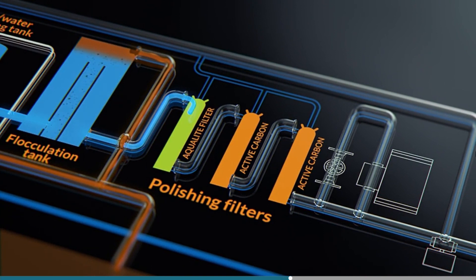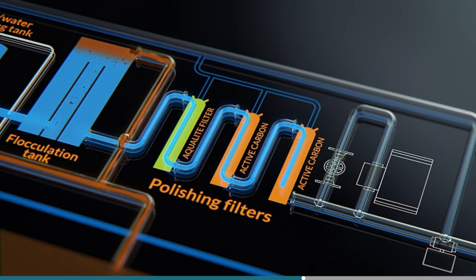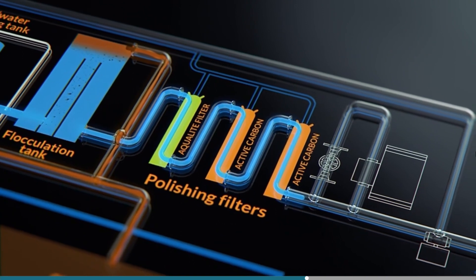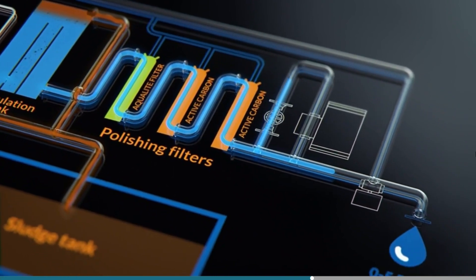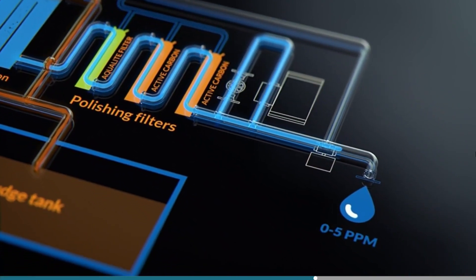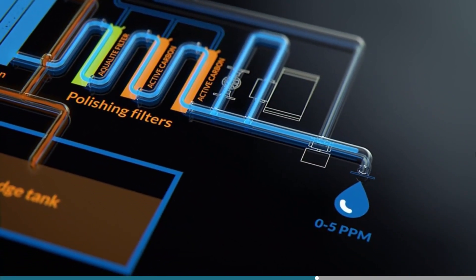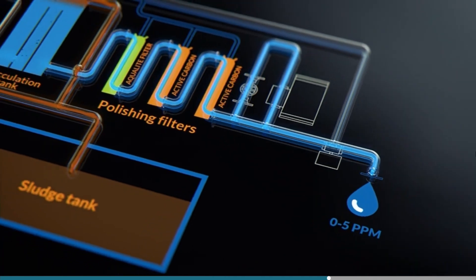The first stage is filled with a coarse sand filtering medium, Aqualite mineral, and the next two stages are filled with active carbon. The clean water leaving the polishing filters can then be discharged via the separator discharge monitoring equipment and an automatic stop and recirculating valve. Used correctly, a discharge of 0–5 ppm can be obtained.